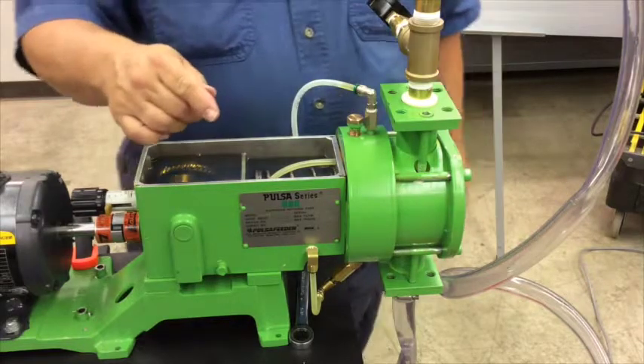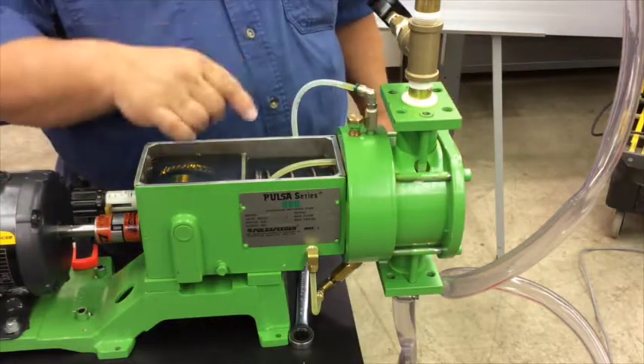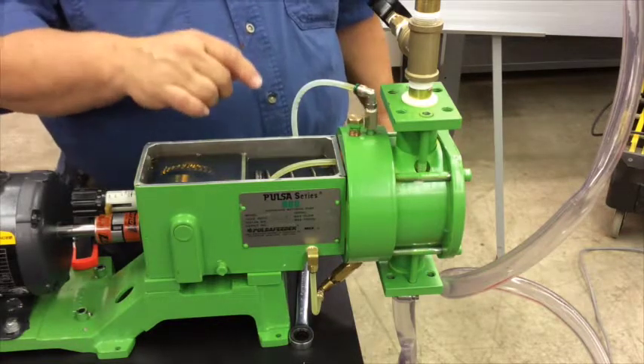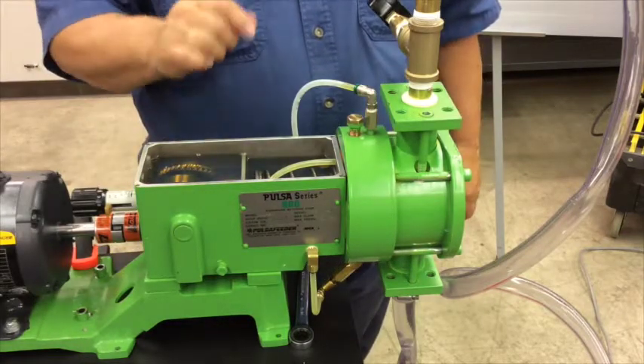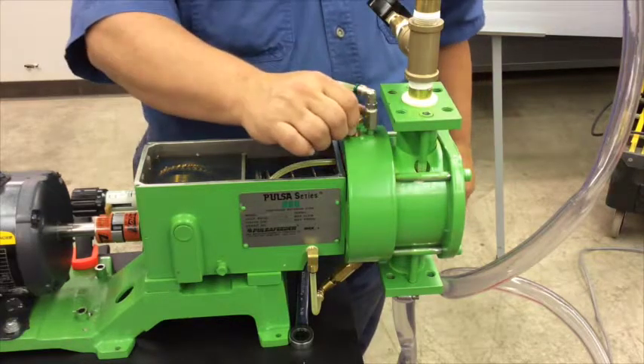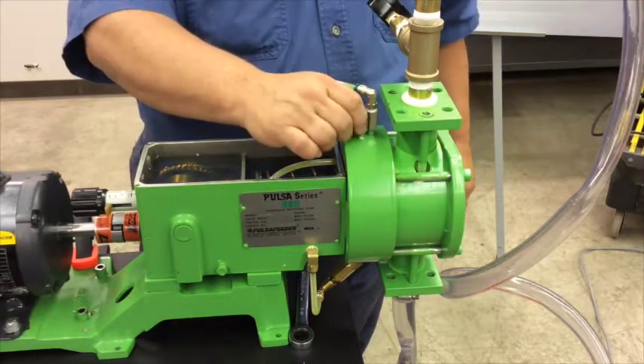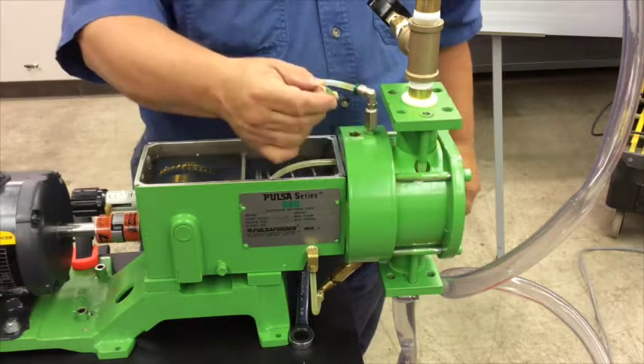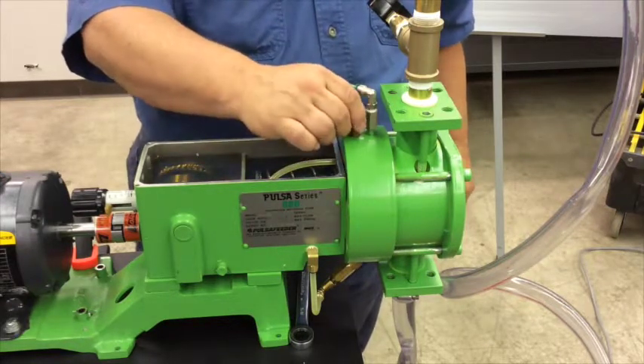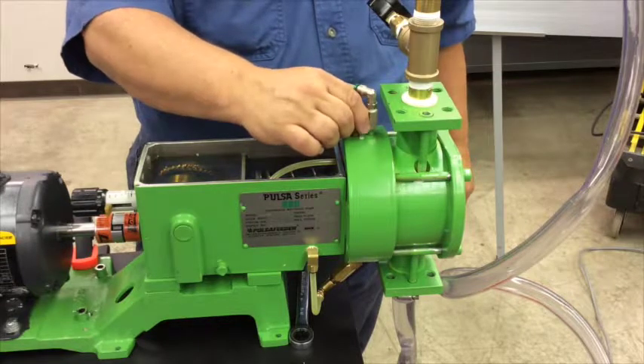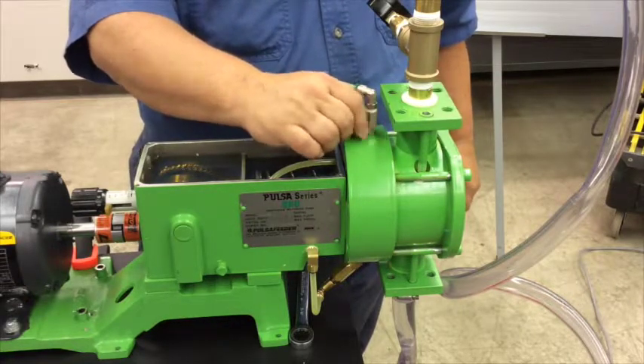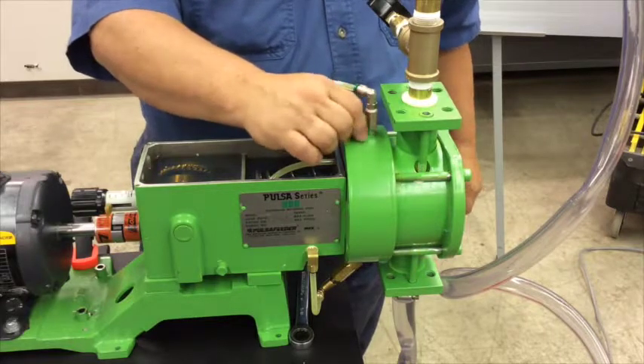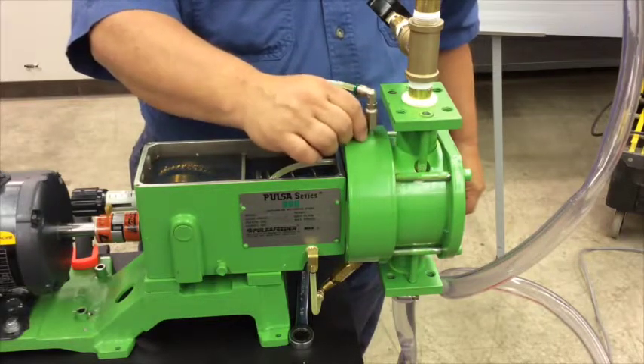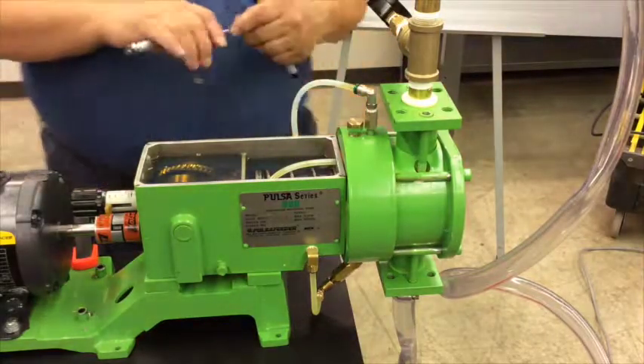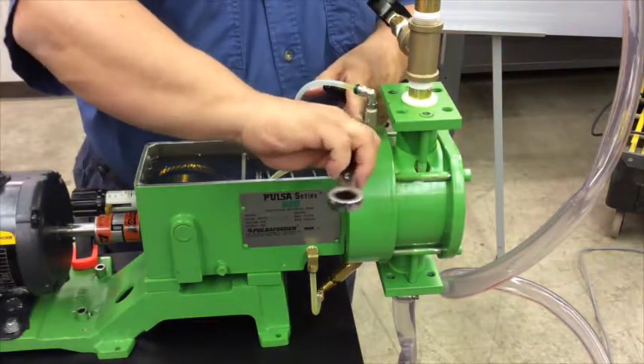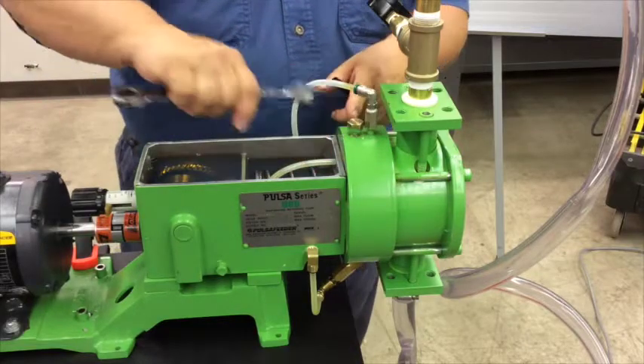Okay, we're in the final adjustment of this pump. If you recall, we removed the hydraulic bypass adjustment screw, and we counted the number of turns, and it was 6 turns from where it was set. So I'm going to now remove the screw to establish my starting point. Okay, I have it in my hands. I'm going to put it back in, and now I'm going to count those 6 turns. So 1, 2, 3, 4, 5, and 6. And it's just getting a little tight there, so I'm just going to give it a little tightness with a wrench here. Great. Very good.